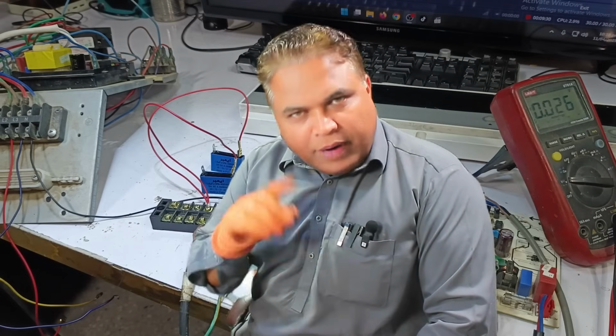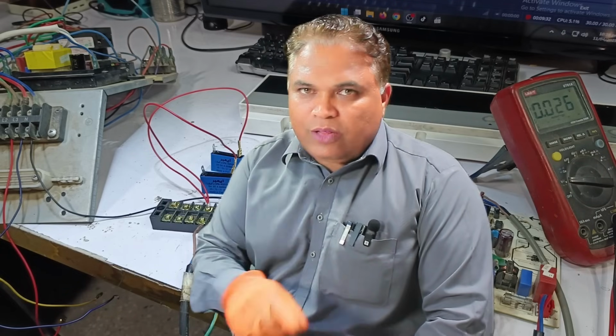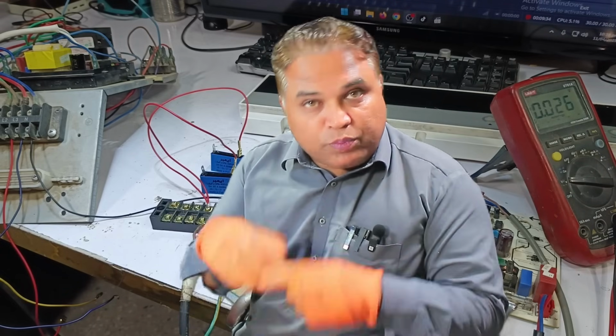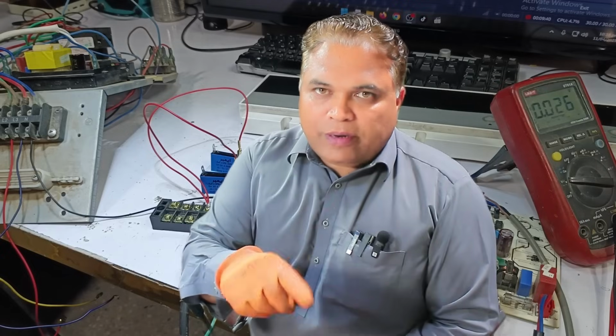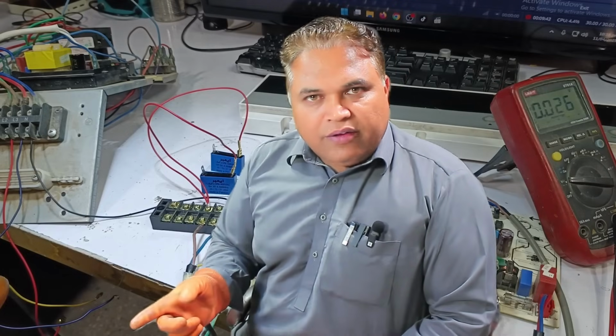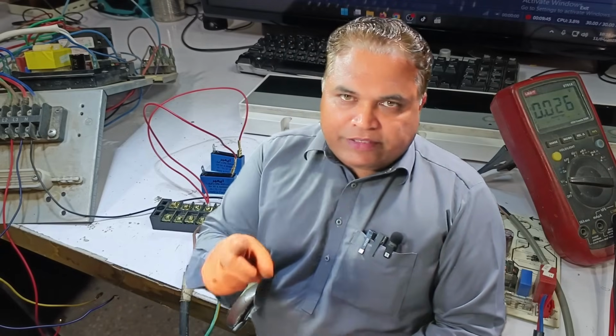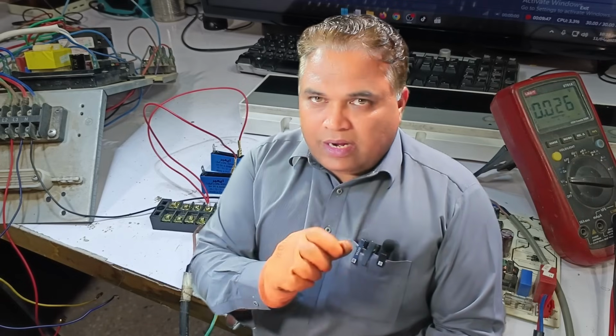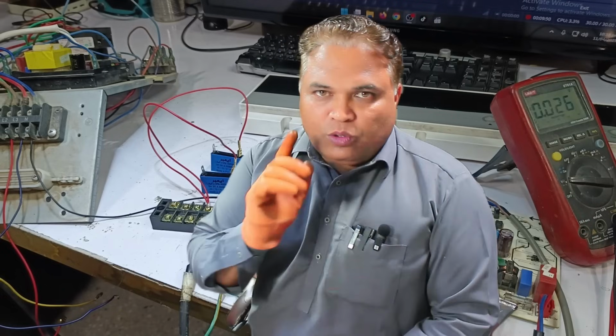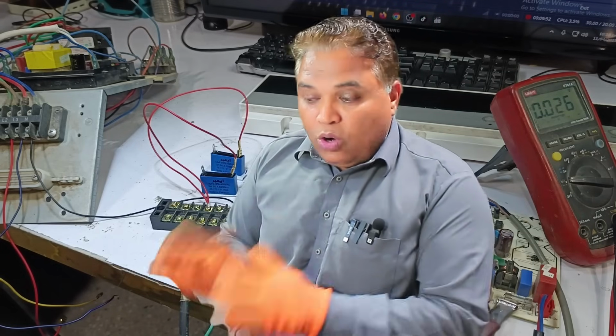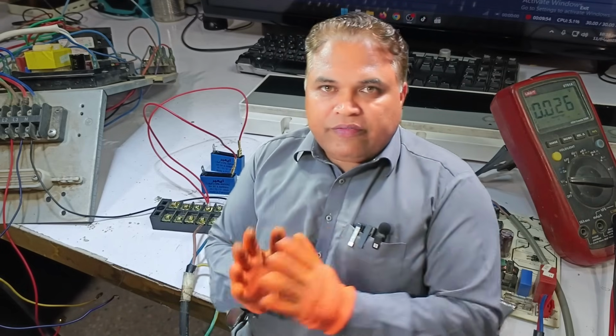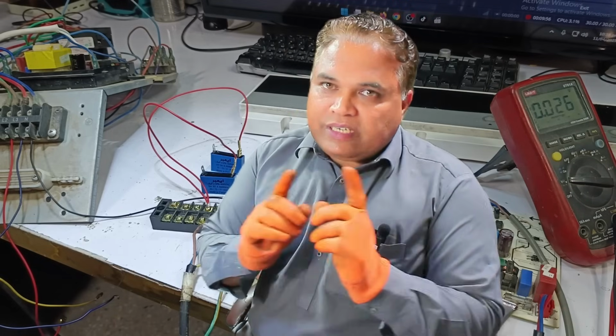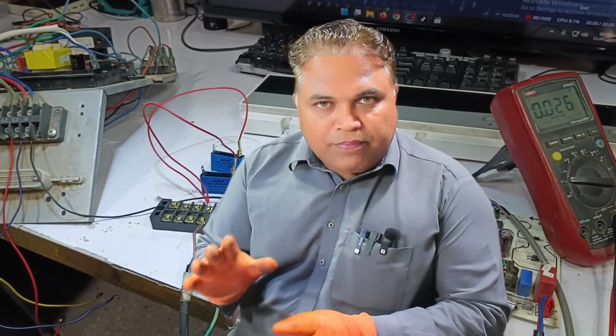The work that I have done afterward. If you are performing this procedure yourself, you should first do the voltage testing before proceeding further. Also, you must confirm on the capacitors that the same voltage you are receiving from the single-phase supply is appearing at the capacitor outputs as well. If the same voltage is not appearing, it means the capacitor you are using might be faulty, and you should replace it. Only after confirming this should you proceed with phase testing or PCB testing.